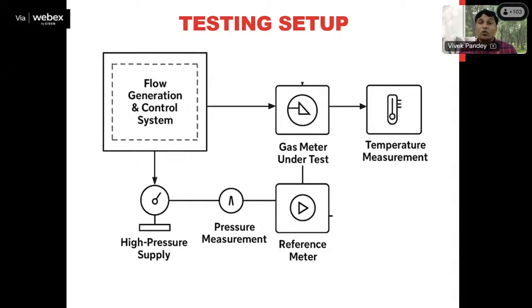And to control the flow of gas through the gas meter as well as the reference meter, that is, at what flow rate we are going to perform the testing, we need a flow generation and control system, with the help of which we can digitally set up a flow rate. Suppose we want to perform the test at minimum flow rate, we can adjust the values in the flow generation and control system accordingly. And there should be a temperature measurement system, as I already told you, to indicate the temperature level. So this is the system through which we can perform the observations. We can transfer the gas through this system at a certain flow rate, and we can compare the reading of the reference meter and the gas meter to get the percentage error in the indication.